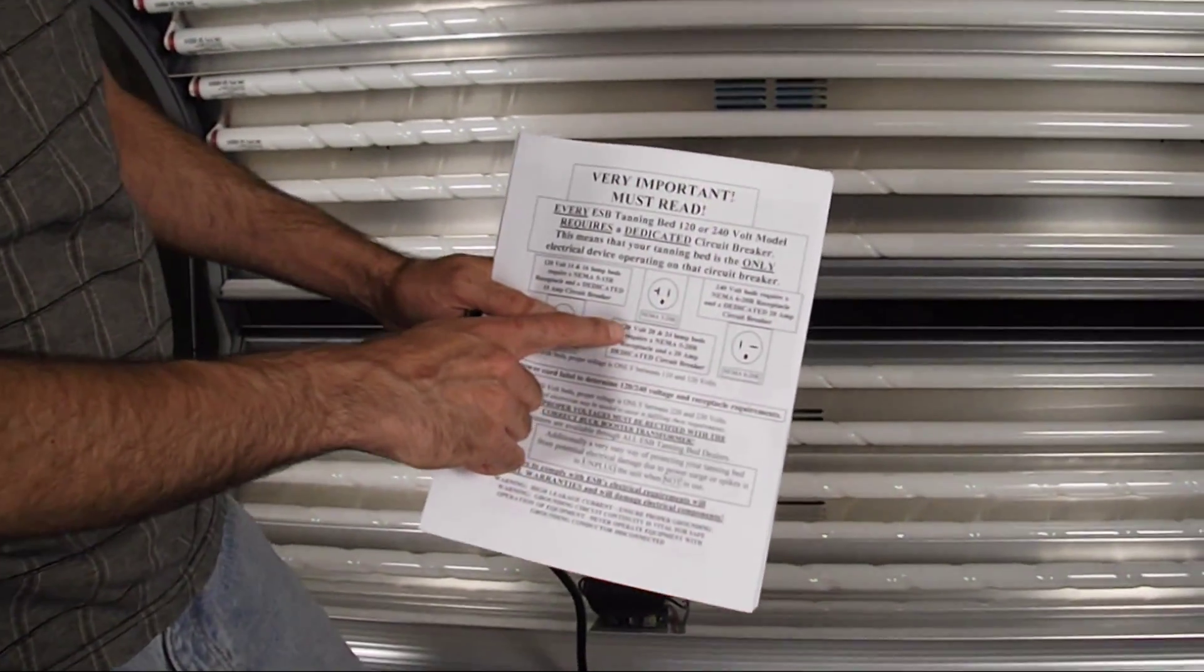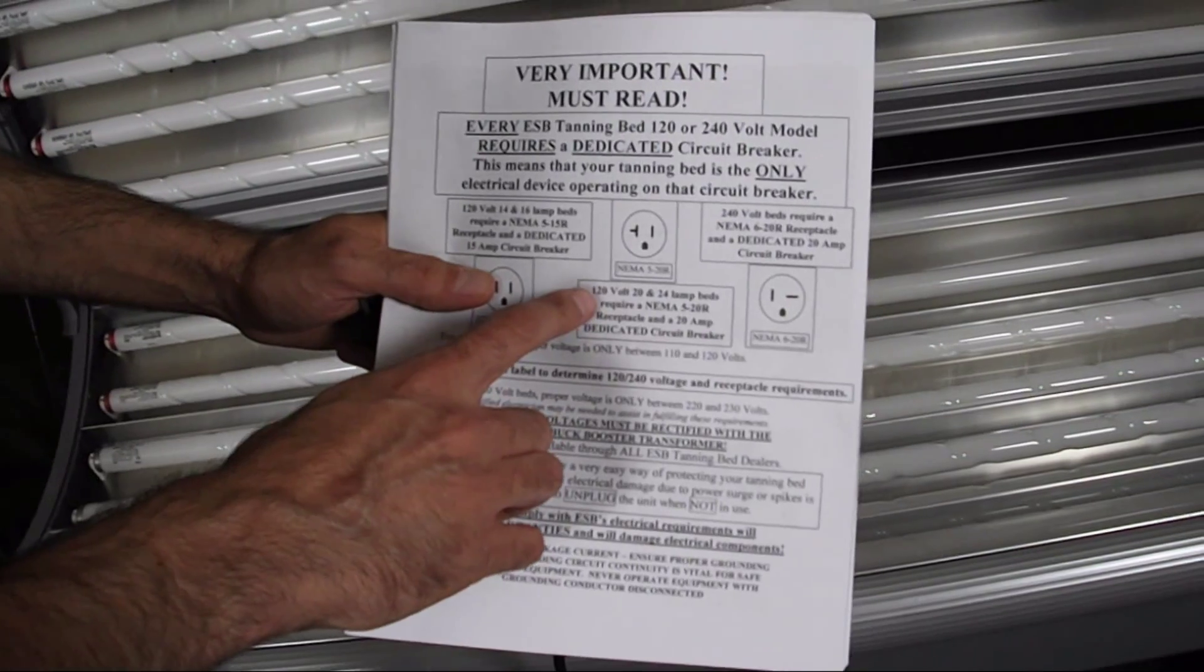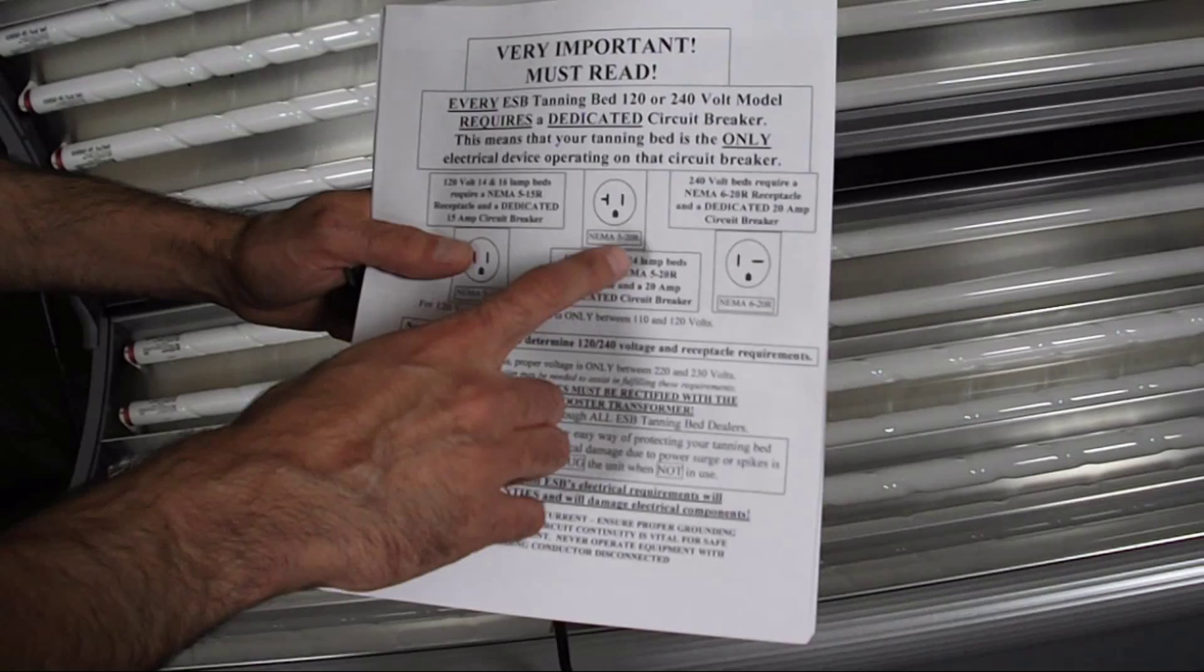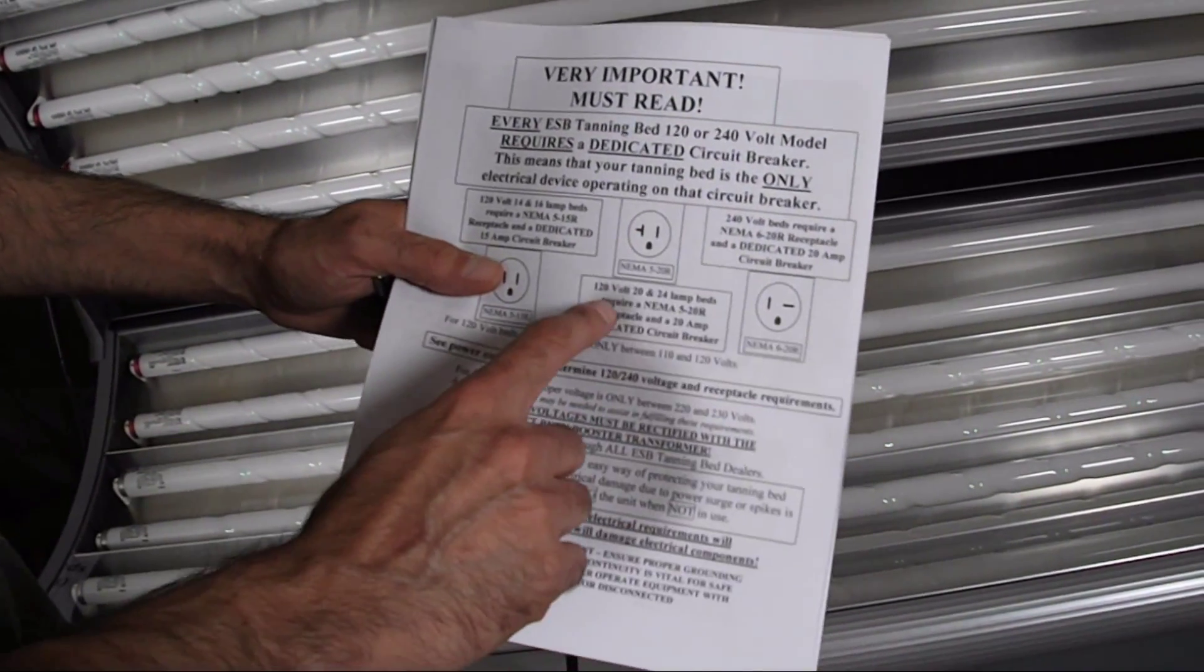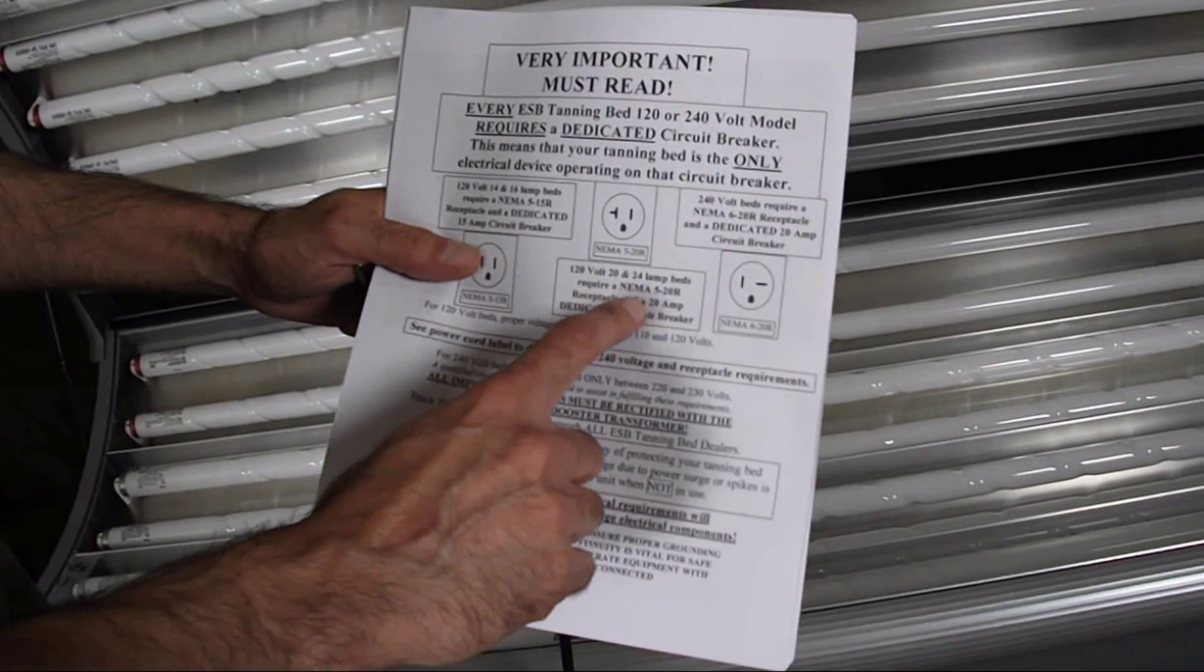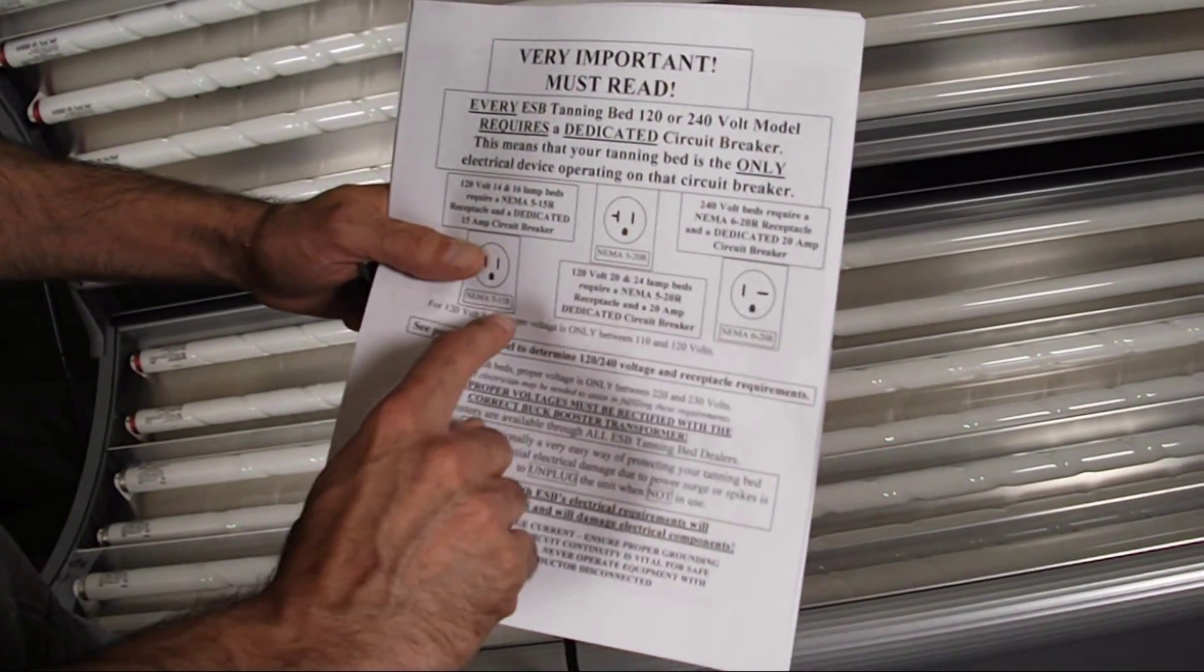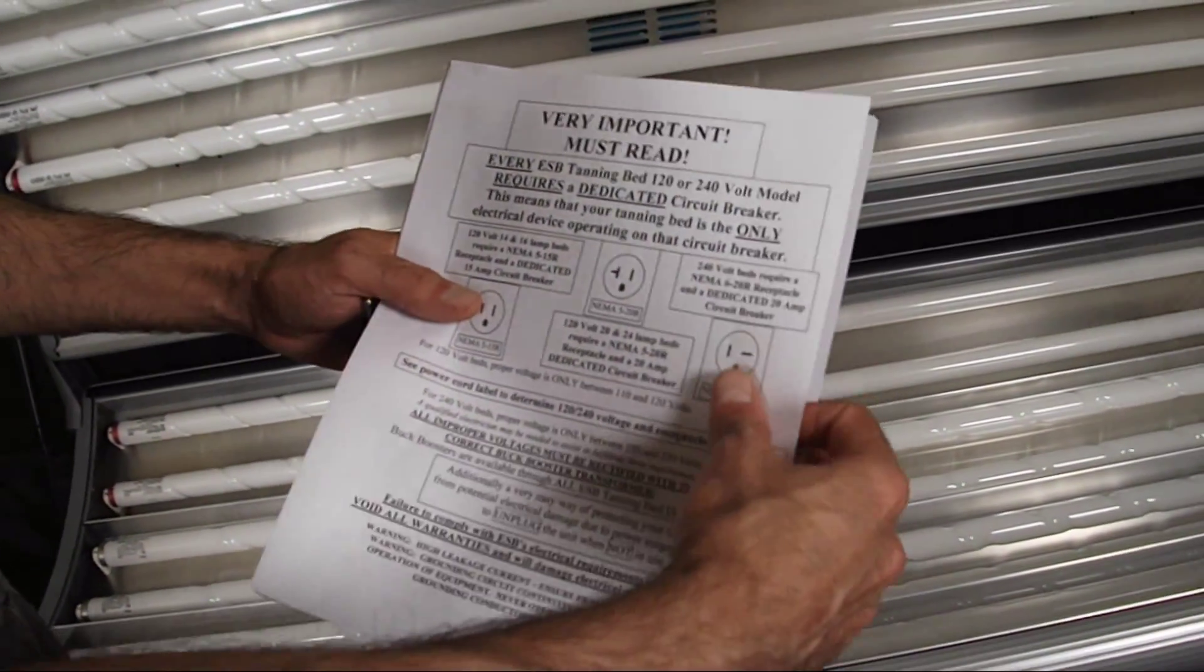Most of the beds will require this, the NEMA 5-20R. This is 120 volt, 20 and 24 lamp beds. There are other configurations that have this type of a plug though, and those require, this is a 20 amp plug, 120 volt, and it would require a 20 amp dedicated circuit breaker just the same.